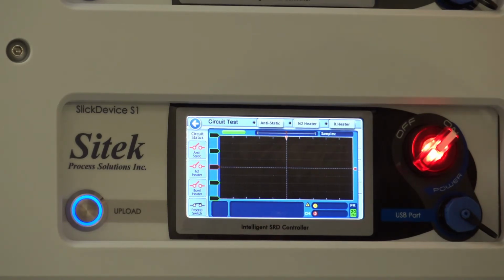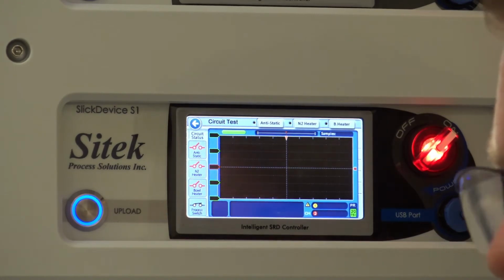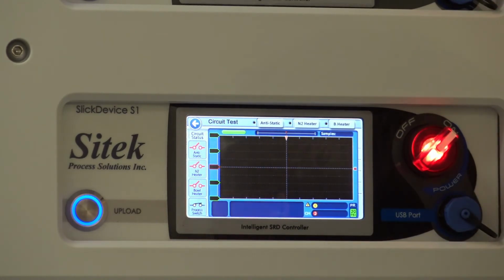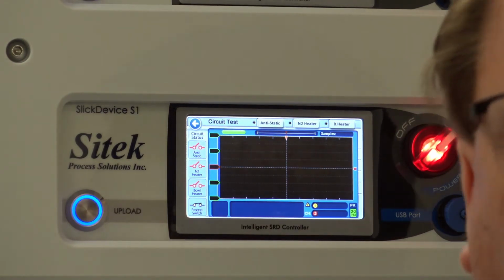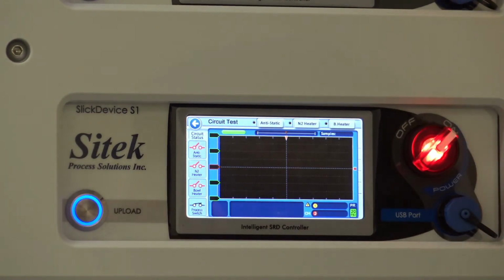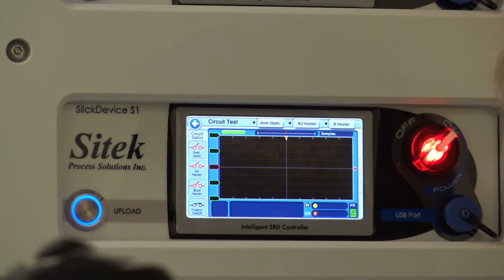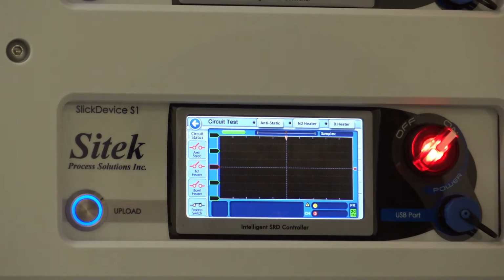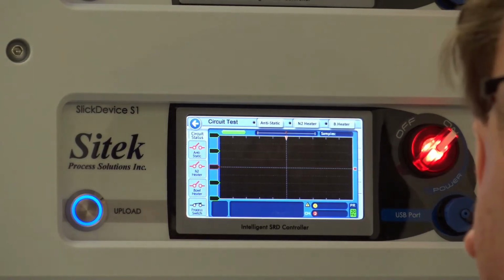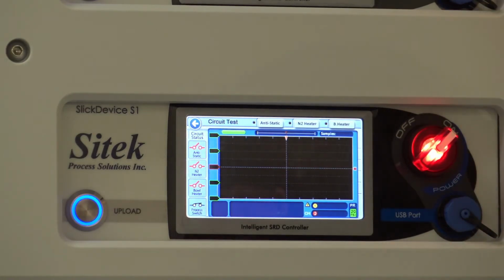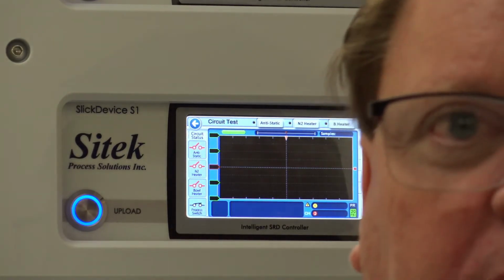The problem is, most people, if they have a traditional rinse and dryer, they don't know their anti-static module went bad. In fact, if you look at a system and it says, to test your anti-static, use a high voltage probe, that doesn't tell you it's working. You might probe, oh yeah, I have high voltage. Probe, I have high voltage. There are some characteristics of an anti-static that have to happen inside, and just because you have a high voltage on the probes doesn't mean it's working correctly. That's part of our DDL algorithm.